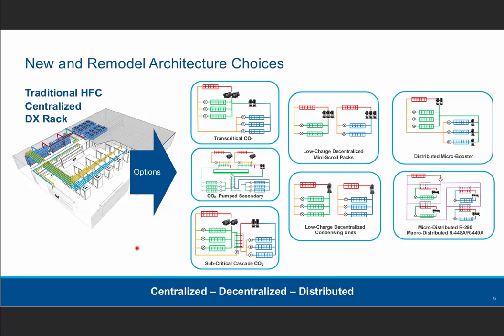HFC losses due to direct emissions and greenhouse gas emissions due to direct. So some of the options that have been proposed and are being actively used today in the centralized space, of course, are CO2 transcritical. And what I've done here with all these diagrams, I've tried to keep them to the lowest common denominator. When we go to school, we talk about the basic four components that you need for a mechanical refrigeration system. So that's how I've tried to lay out these schematics. You've got a compressor, you've got a condenser, you have a pressure reducing device, an expansion valve, and you have an evaporator. So I've tried to keep them as simple as possible.